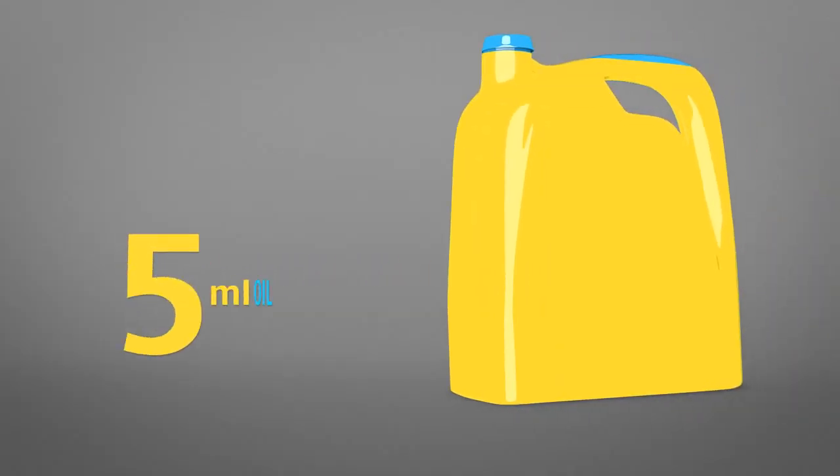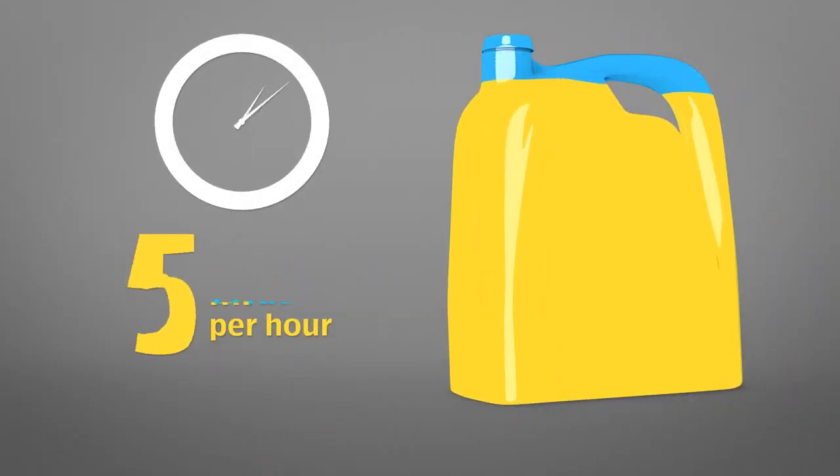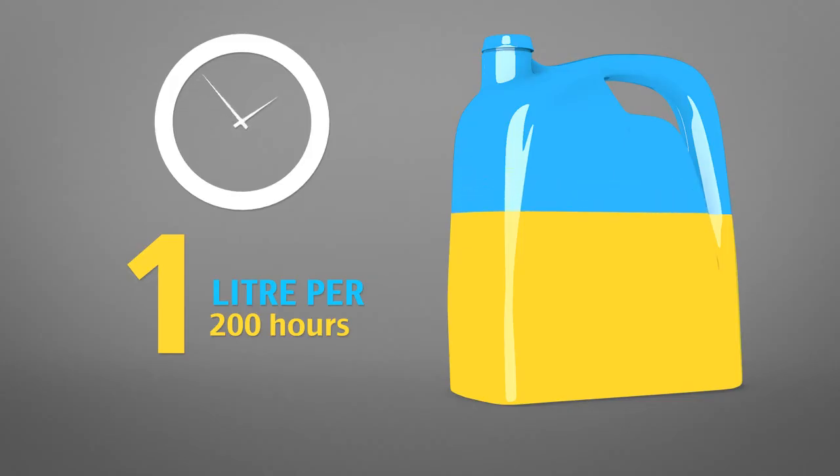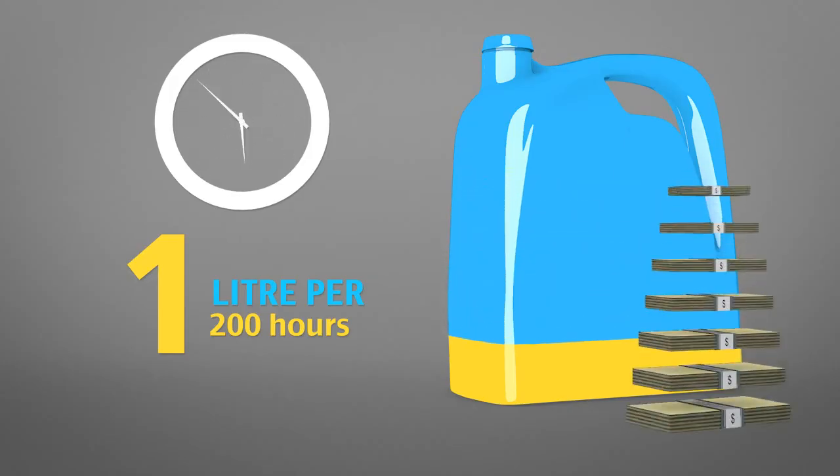A separator losing oil at 6 parts per million could lose around 5 millilitres of oil every hour, or 1 litre every 200 hours, adding more avoidable cost to your annual bill.